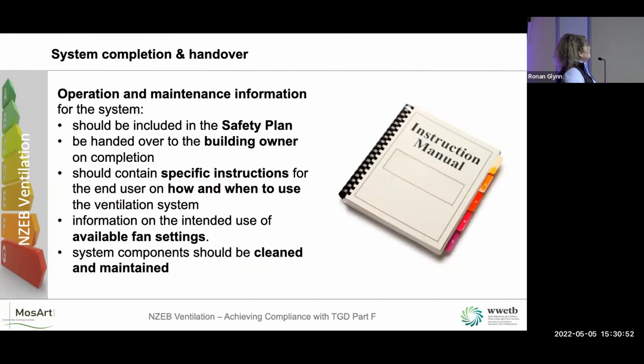Again, the system completion and handover: the operation and maintenance information for the system should be included as part of the safety plan. It should be handed over to the building owner on completion, and it should contain specific instructions for the end user on how and when to use the ventilation system. And that includes that it should never be turned off. It should also give information on the intended use of the available fan settings.